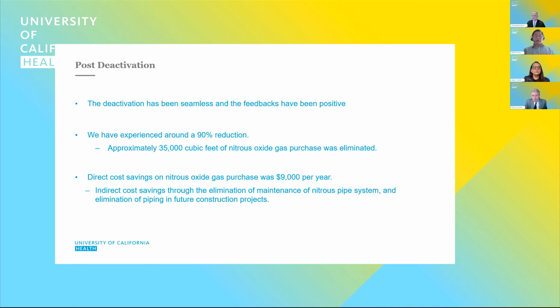So as a result, the deactivation was seamless. There were no surprises or disruption reported. And we have experienced a similar reduction to that reported by Dr. Cheesebro. We have seen around 90% or more reduction in the amount of nitrous oxide that we purchase. So for our side, that results in approximately 35,000 cubic feet of nitrous oxide gas purchased or eliminated, or 537 equivalent tons of CO2 emission.